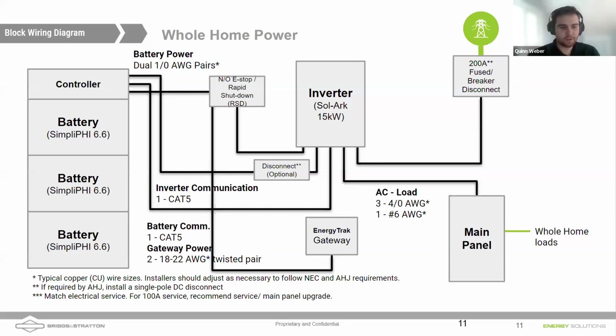This all looks good. The only thing is, I see at the bottom in the three-star match electrical service for 100 amp service, recommended service/main panel upgrade. You can pass 100 amps through a Sol-Ark inverter just as easy. You can pass 200 amps. So, you can back up just like you could back up 100 amp service with the 24 kilowatt generator. You could do the same thing with the Sol-Ark 15K. But these look correct. Great. So thank you for that.